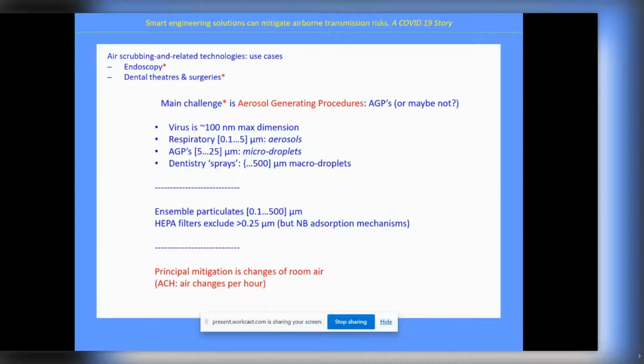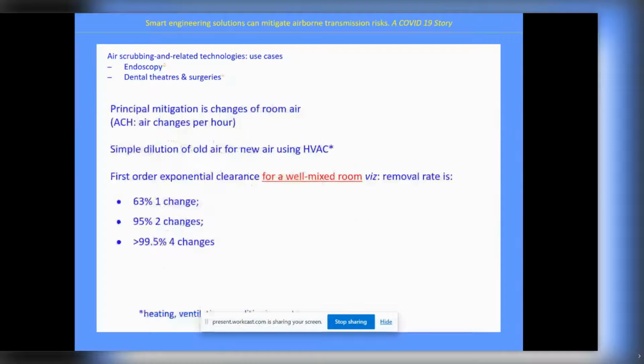The principal mitigation for dirty air is changing it, the number of ACH, air changes per hour, you can achieve. Simple dilution conventionally uses the hospital's heating, ventilation and air conditioning unit, and it falls off as simple dilution, a first order exponential equation for a well-mixed reactive room.